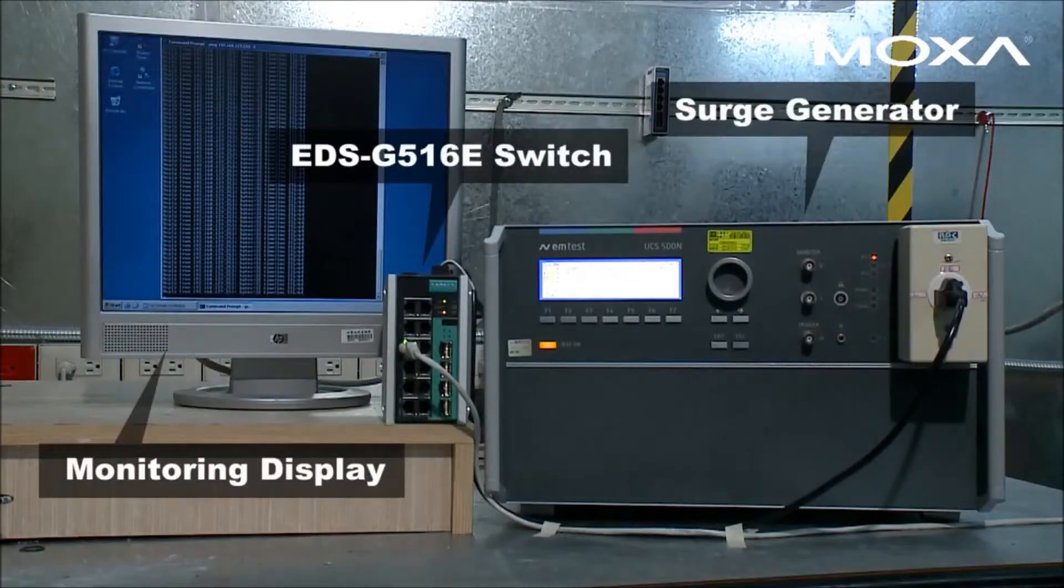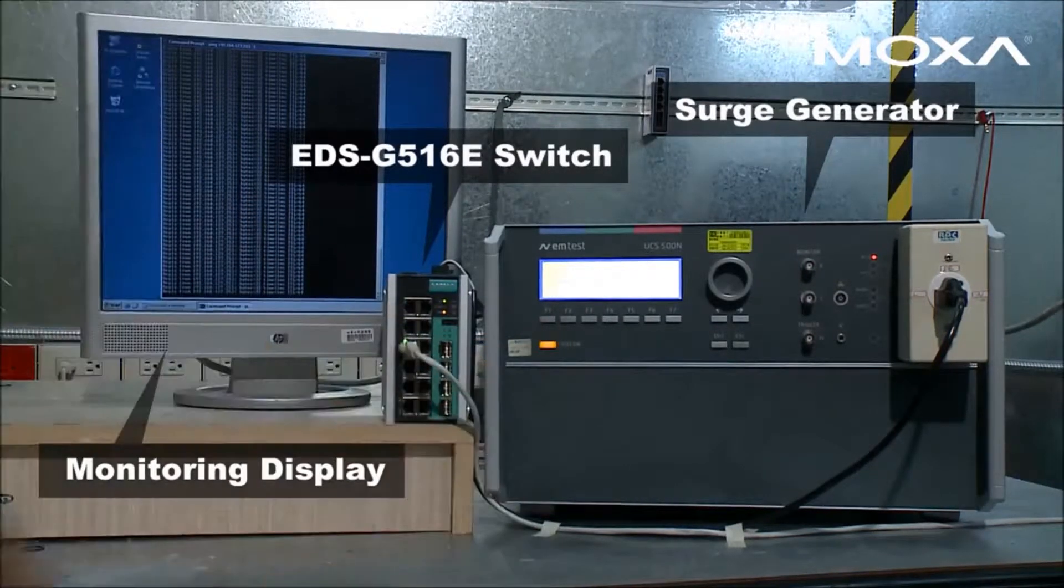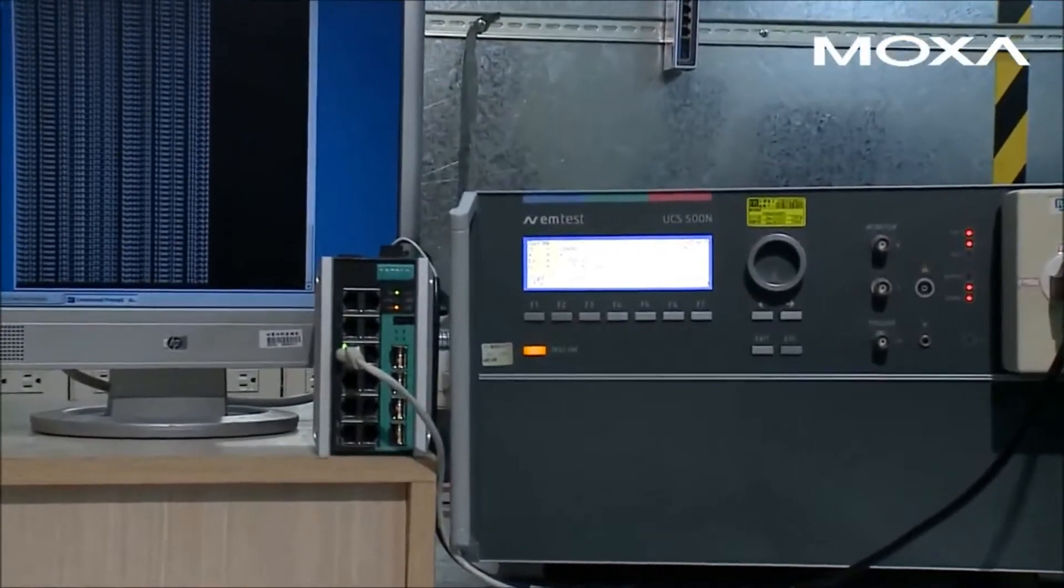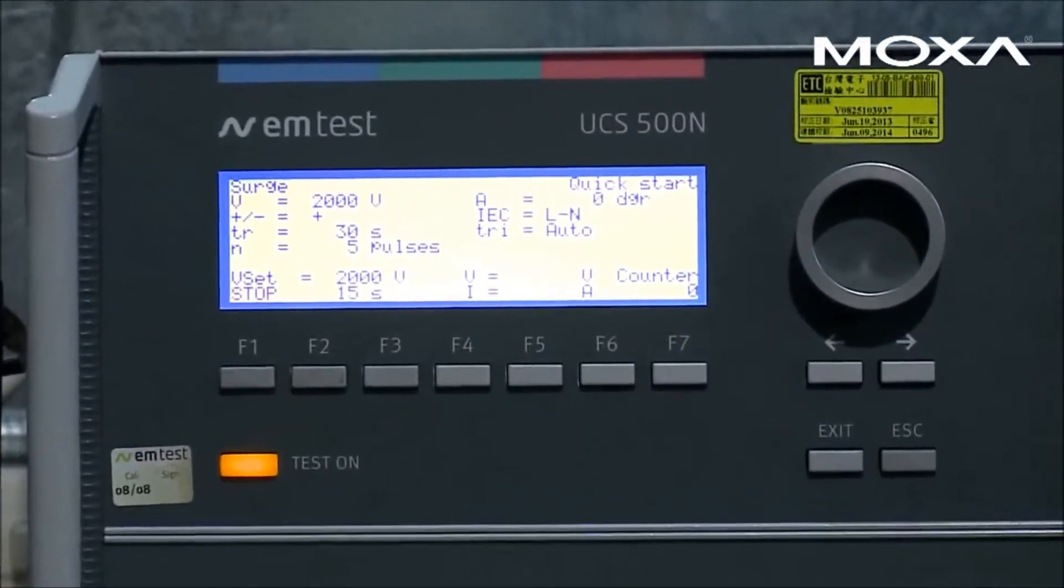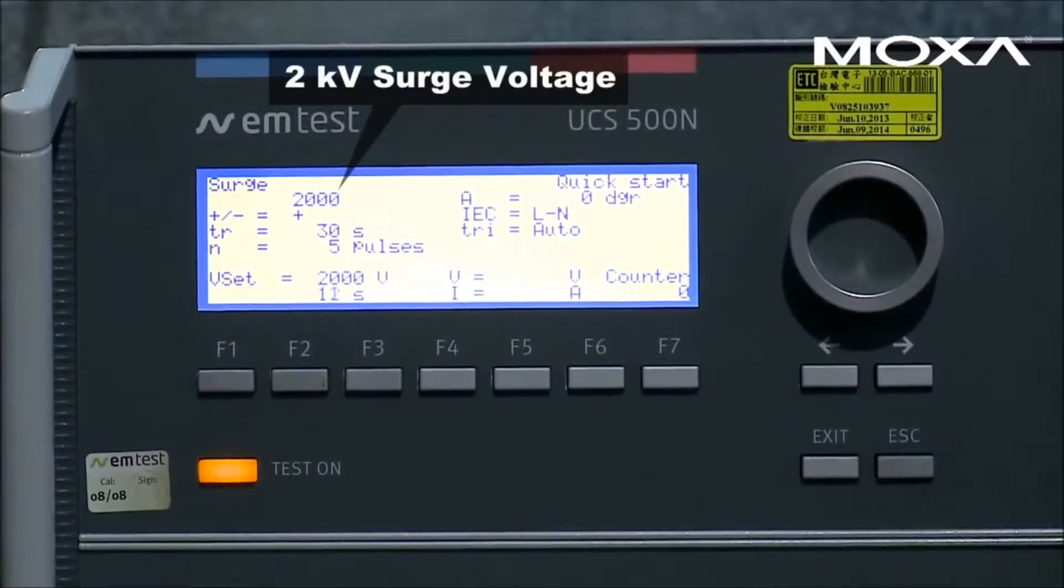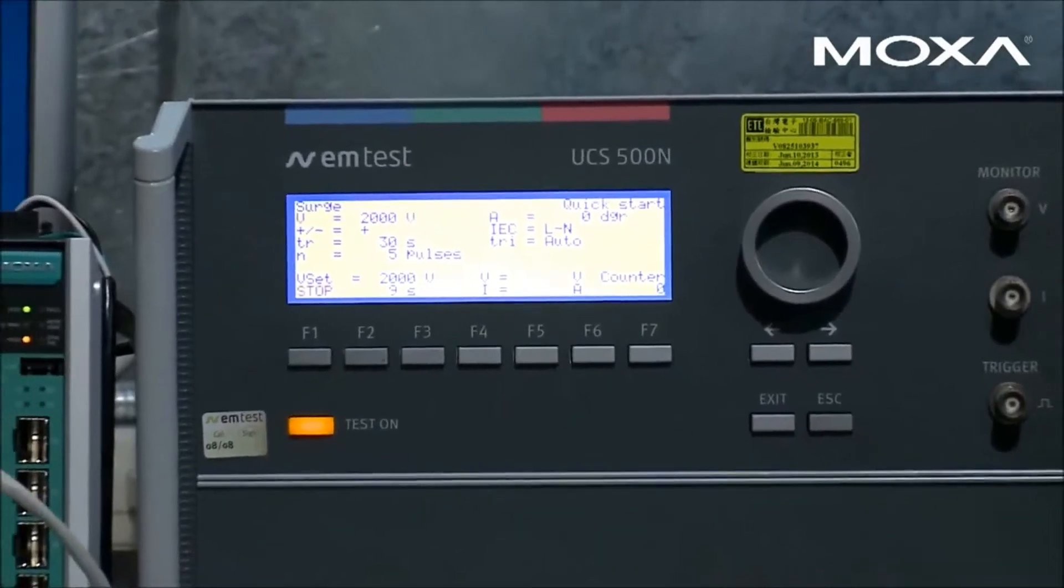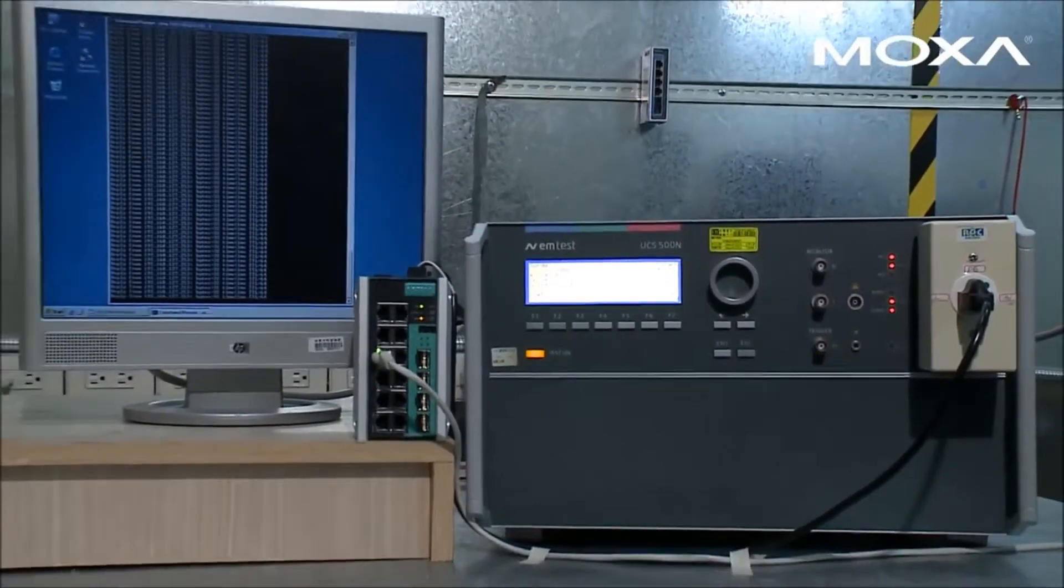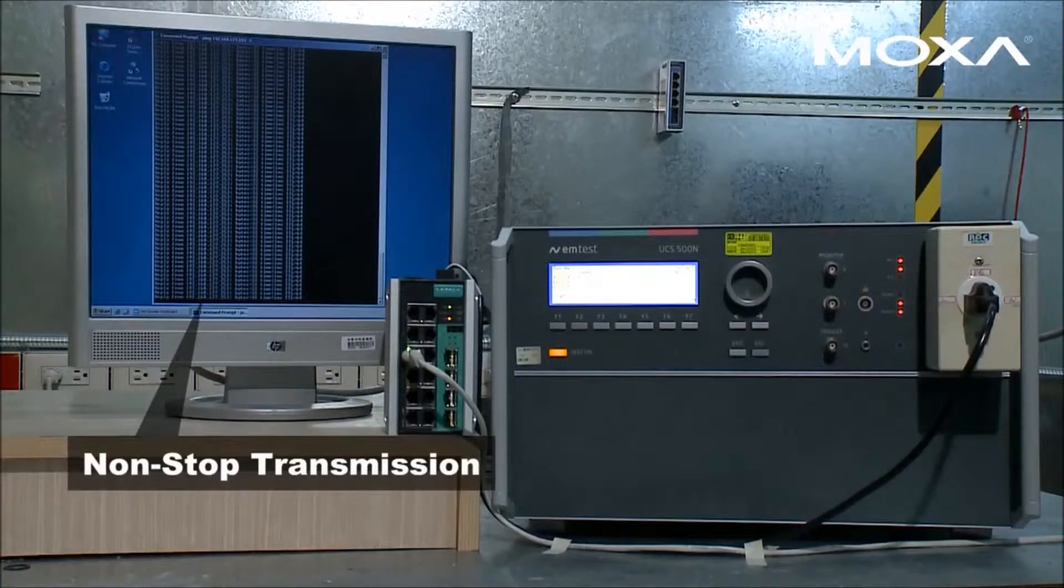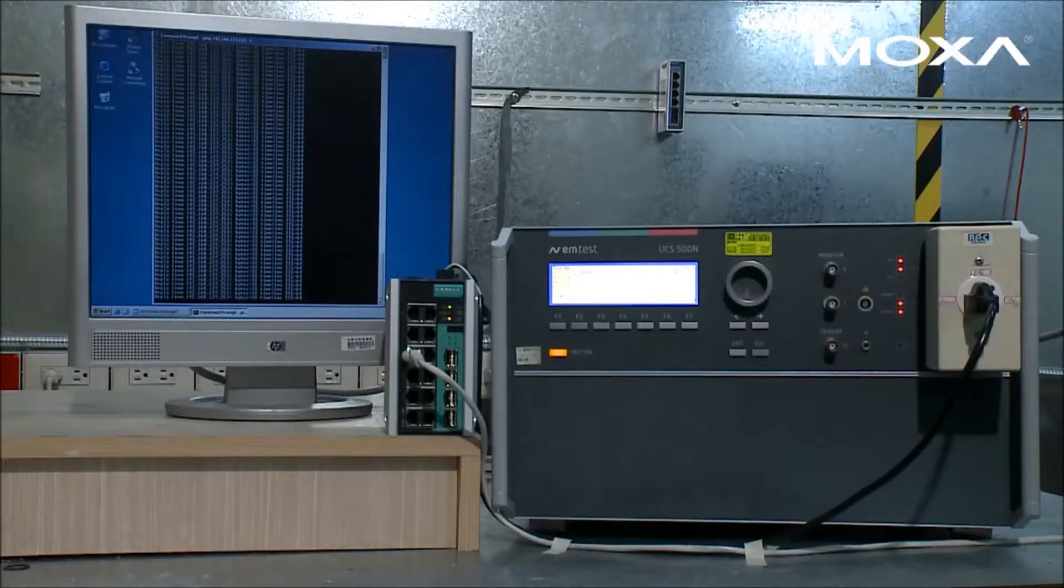Surge can be caused by a short circuit, lightning strike, or power outage recovery, and can generate intense heat, burn wire installations, and even cause fires and explosions. To verify surge immunity, IEC-compliant testing methods were applied for this surge test. The switch was able to repel a 4 kilovolt surge injection and continue operating unaffected. This level of surge immunity makes the EDS E-Series switch an ideal choice for substation environments.